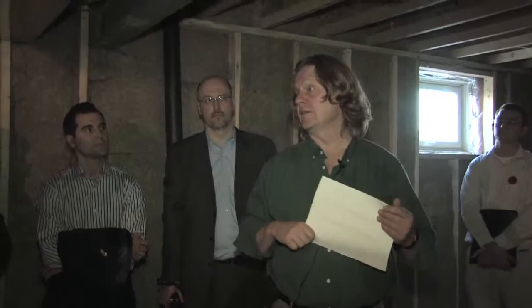The boiler is fully modulating — it's like the accelerator in your car. Right now it thinks it's a hot water tank, so it's only giving us 45,000 BTUs. In the winter we can get up to about 99,000 BTUs out of it. The thing to understand about this house is that on the coldest day of the year we only need 25,000 BTUs, and 50% of that is coming from the sun — so that boiler probably isn't going to be running on a sunny day.